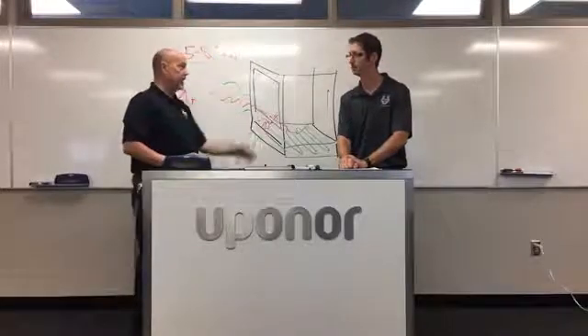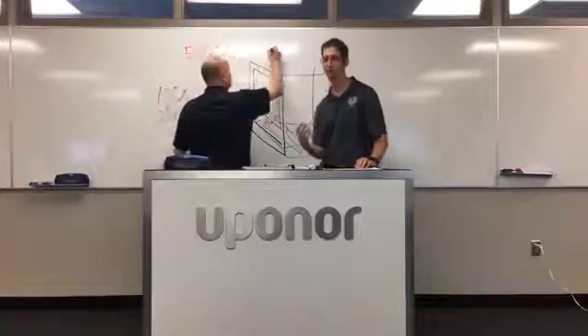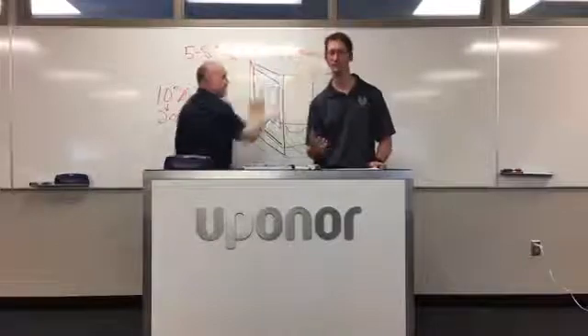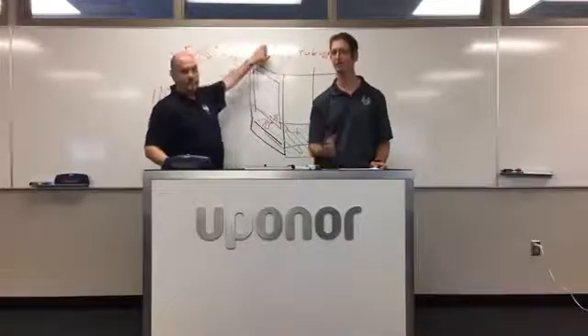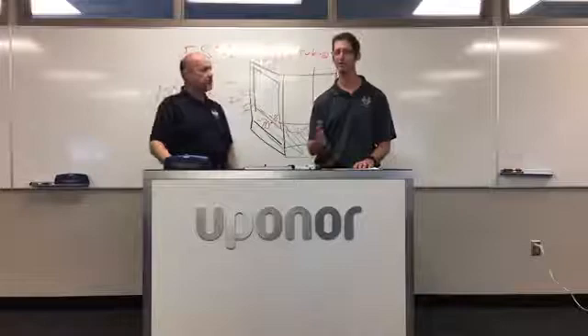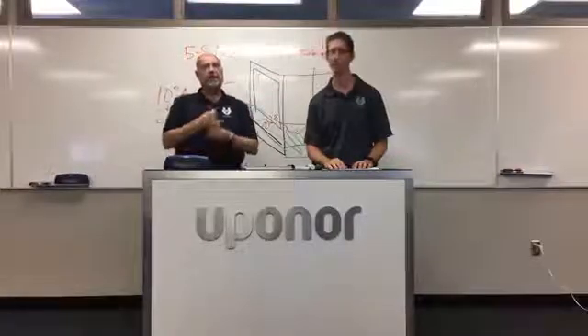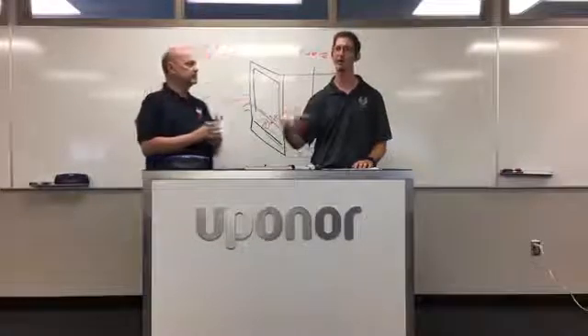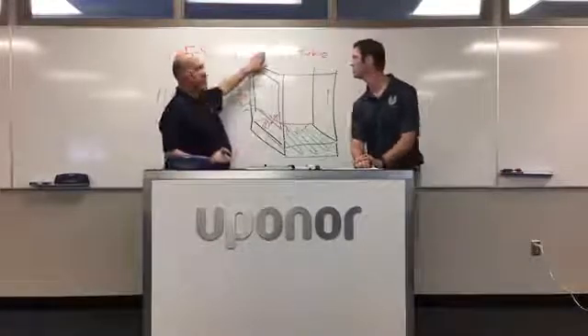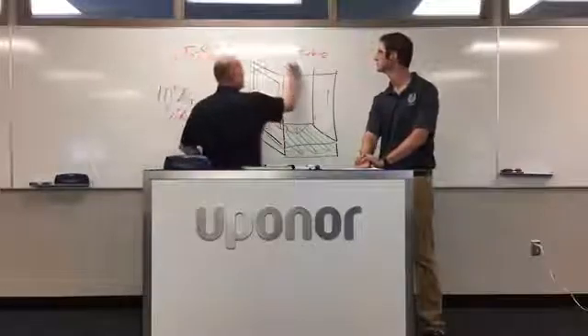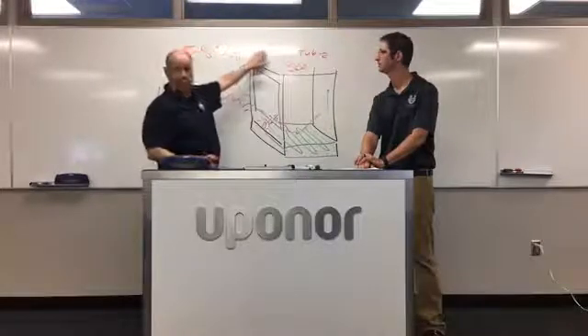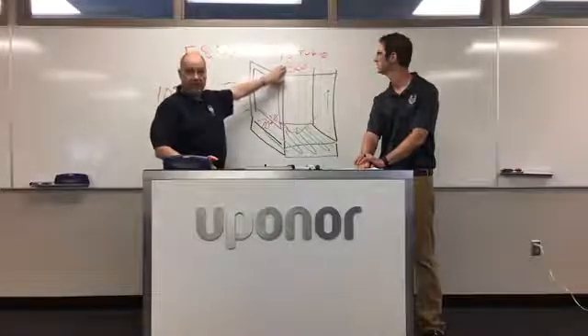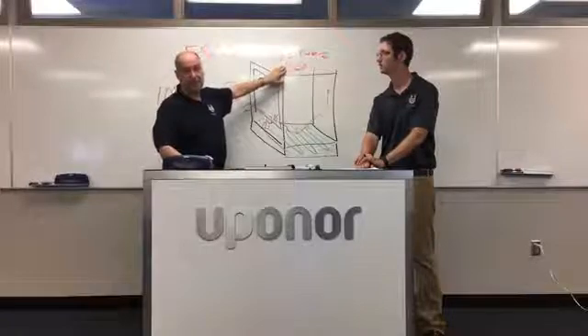We can compensate by switching from half-inch tubing to five-eighths inch tubing. As a rule of thumb, five-eighths or three-quarter inch tubing is a good benchmark for cooling — it keeps your circulators small and cuts down on energy consumption over the lifetime of the system. Shorten your loop lengths to 300 feet for five-eighths tubing; in heating we run up to 450 feet, but 300 feet makes your pump work less.